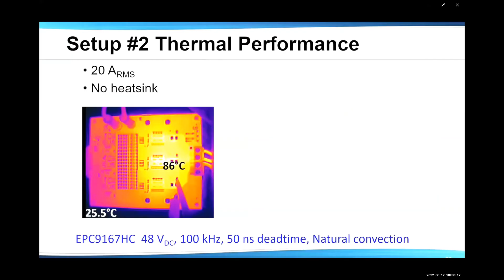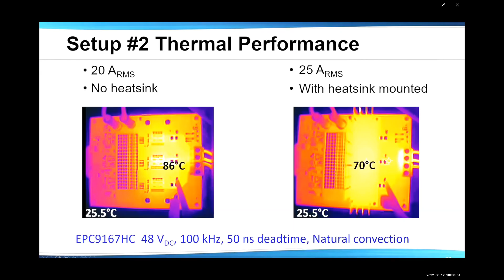In the 9167 HC, without a heat sink, we can easily get 20 amps RMS, with about 60 degrees delta. By putting a heat sink we can reach less than 50 degrees delta, because we measure the heat sink temperature and consider the devices to be slightly hotter. We can reach 25 amps RMS with this board at 100 kilohertz, 50 nanosecond dead time, with natural convection.